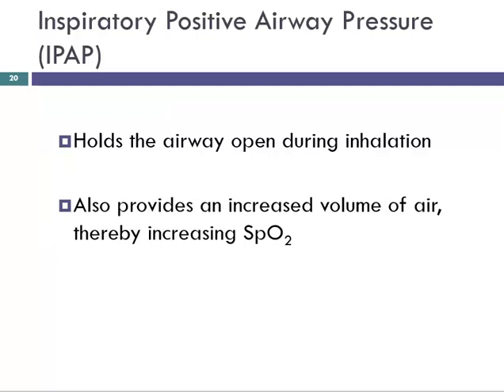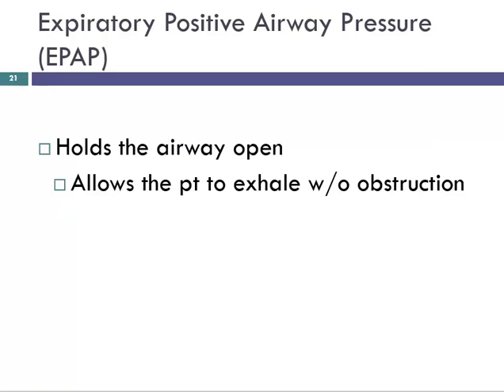Inspiratory pressure holds the airway open, gives that augmented tidal volume, lets the patient breathe in a bigger volume of air, so it can increase their saturation, and it's mainly used to treat the hypopneas, the RERAs, that type of thing. Whereas your EPAP, or your expiratory pressure, is what holds the airway open throughout the entire respiratory phase. So you don't have that collapsing as the person exhales. And so that's mainly used to treat the obstructive apneas if we're using it to treat both.